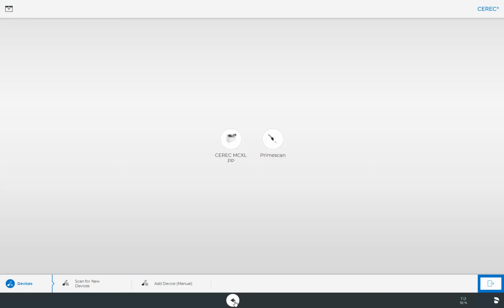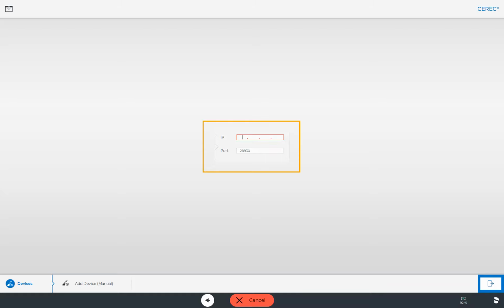In the unlikely event that the CEREC software does not recognize the device, you can connect the grinding and milling unit manually. To do this, enter the IP number of the corresponding device, then confirm with OK.